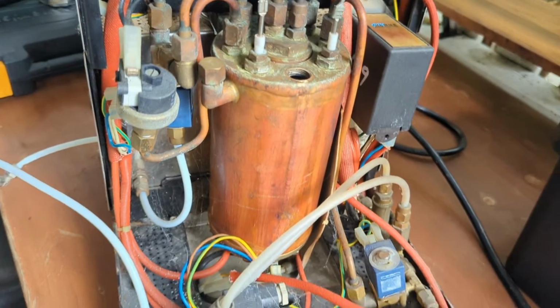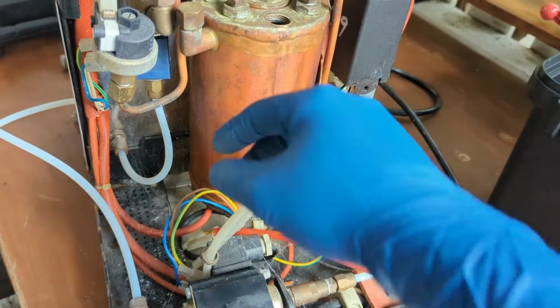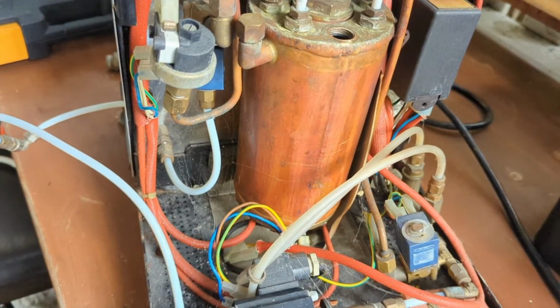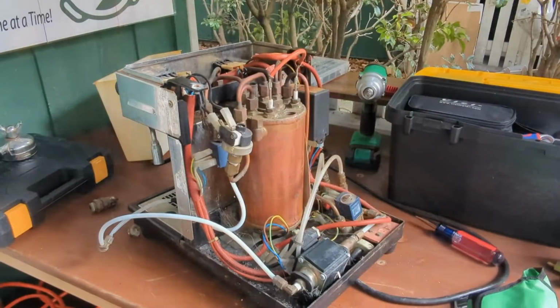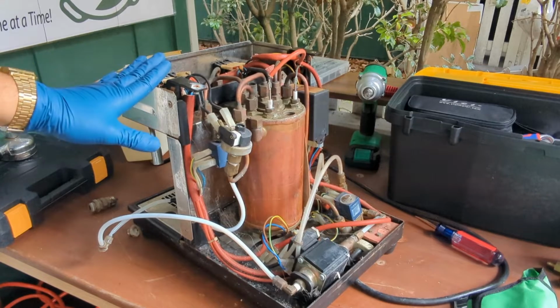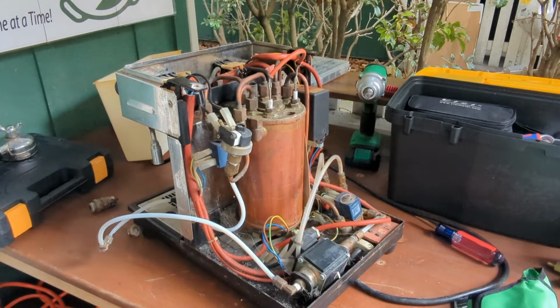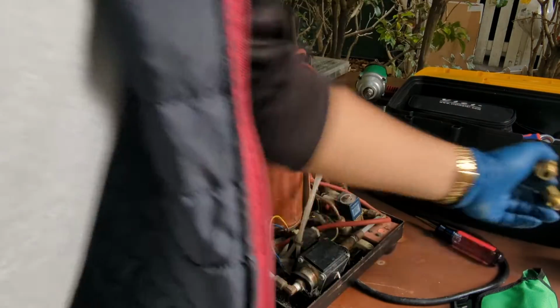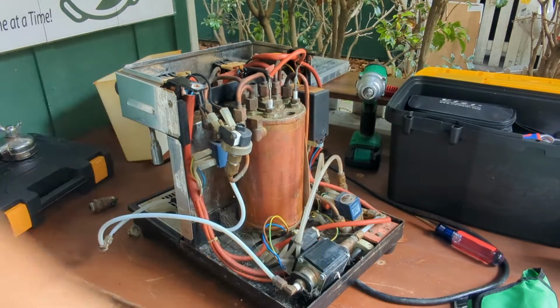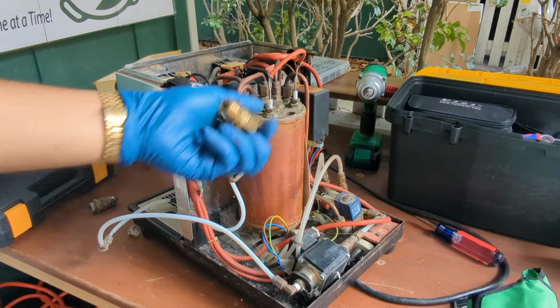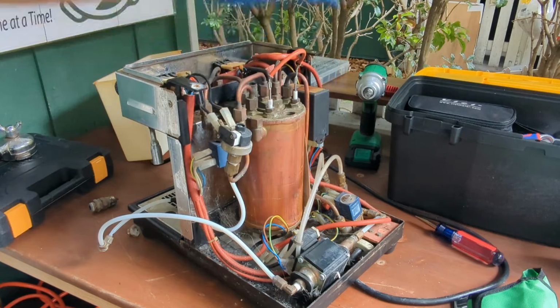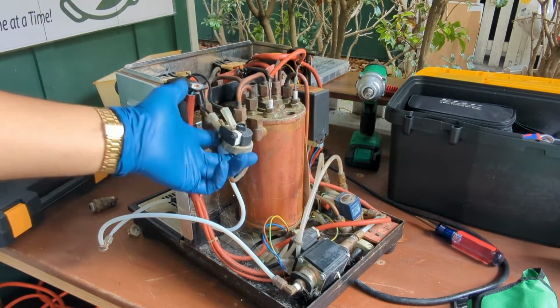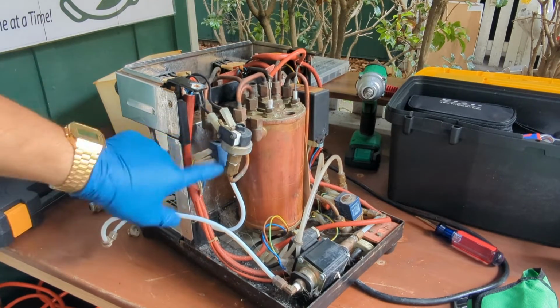And we're gonna be taking out a lot of these copper pipes because unfortunately this boiler is full of scale. So yeah, that's the condition of the machine. That's basically the very basics that we need to do on this one. Replace the water pump, replace the vacuum release valve, replace the boiler safety valve, disassemble all these parts, deep clean it, replace the pressure stat, deep clean the two-way valve.